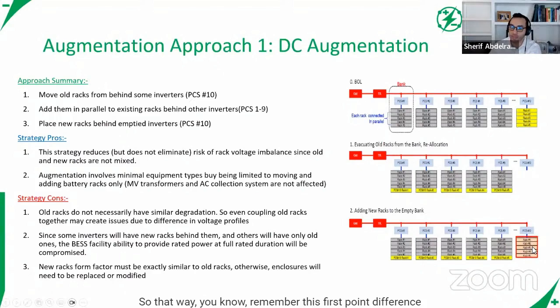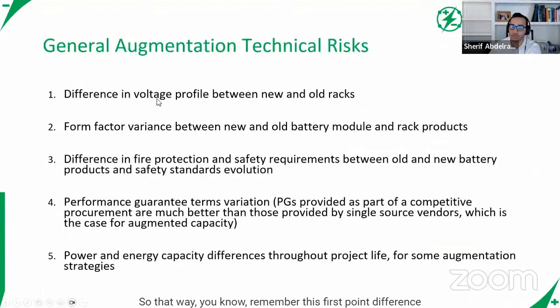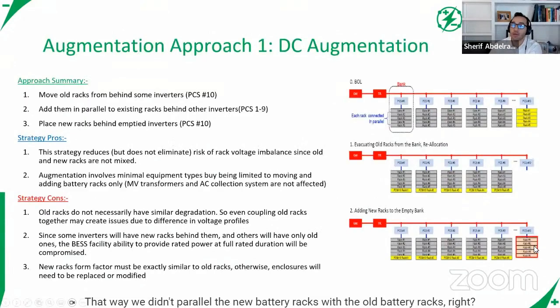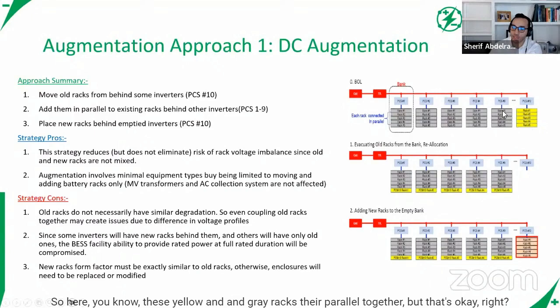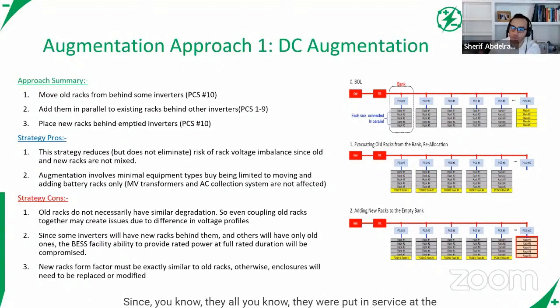And the new battery racks, we add them behind inverter number 10. So remember the difference in voltage profile between new and old battery racks - that way we didn't parallel the new racks with the old ones. These yellow and gray racks are paralleled together, but that's okay since they were put in service at the same time, so they must have degraded the same exact way, right? Well, no, wrong. That's a very dangerous and optimistic view.